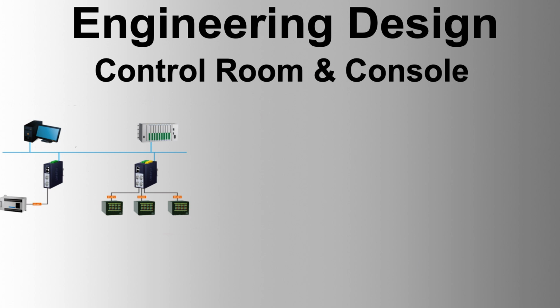Consoles should be located to avoid annoying reflections on the screen. The lighting plan should be drawn up after the console layout is determined. Arrangement of consoles next to one another or at right angles in a U-shape or C-shape depends on the number of operators and the functional relationship between process parts. Each arrangement has specific pros and cons. The maximum number of VDUs an operator can manage in an upset situation is 3. Determining the console configuration. Further guidance on control desks is provided in relevant standards.